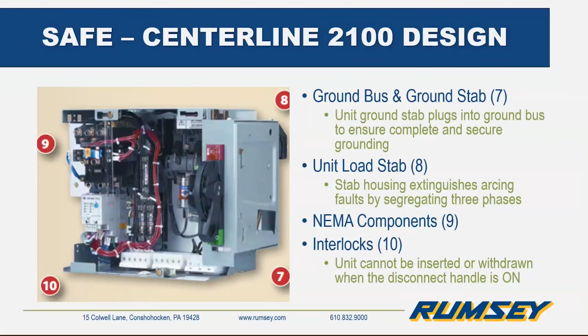Continuing on the design, CENTERLINE MCCs got their name from the unique location of the horizontal power bus, which is right in the center of the MCC, distributing power to each vertical section. The location of this bus accomplishes a few things. First, from a practical standpoint, it allows for a 300 amp rating above and below the horizontal bus, for an effective 600 amp rating in each vertical section. For a long time, Allen Bradley was the only manufacturer to accomplish this.